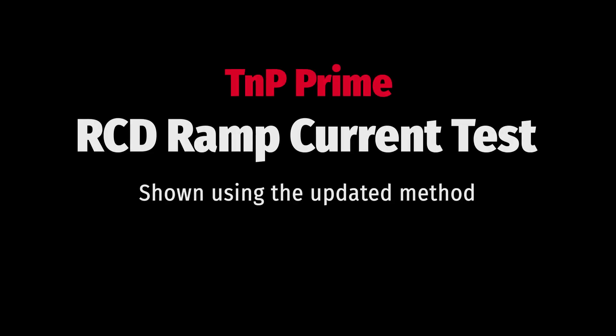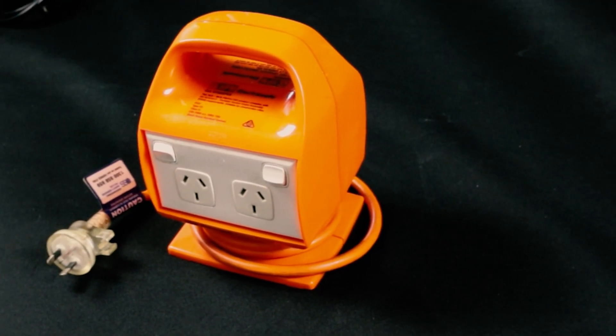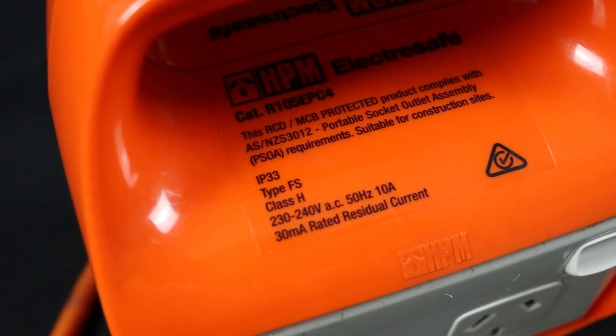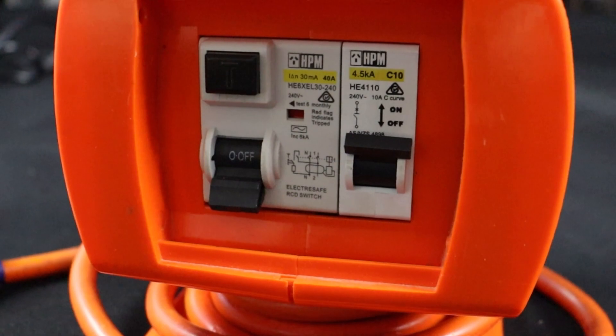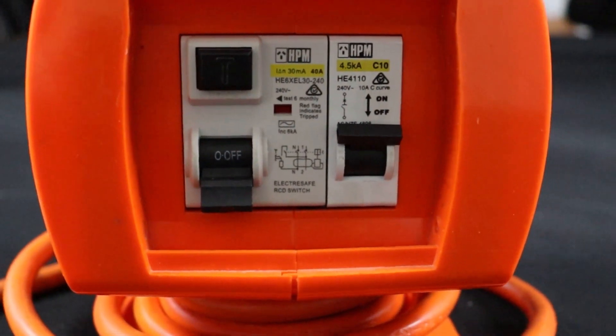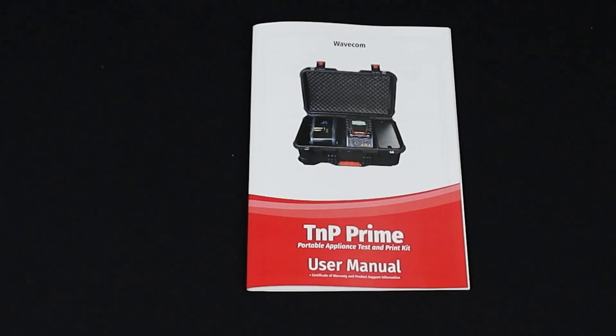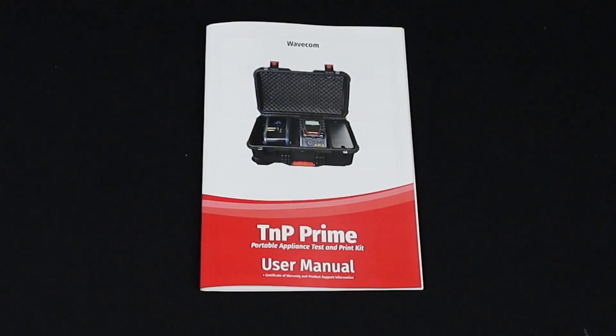Let's move on to testing portable RCDs. We'll start with a ramp current test. First, conduct your visual inspection and determine what type of RCD you have. This example is a Type FS portable RCD. Set up your test leads. In this example, we are using the updated test method. If in doubt, consult your TNP Prime user manual.